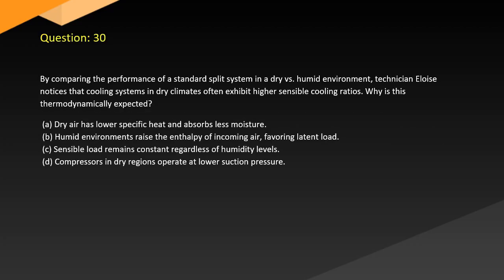Question 30. By comparing the performance of a standard split system in a dry versus humid environment, technician Eloise notices that cooling systems in dry climates often exhibit higher sensible cooling ratios. Why is this thermodynamically expected? A. Dry air has lower specific heat and absorbs less moisture. B. Humid environments raise the enthalpy of incoming air, favoring latent load. C. Sensible load remains constant regardless of humidity levels. D. Compressors in dry regions operate at lower suction pressure.